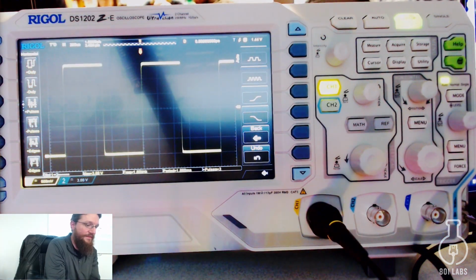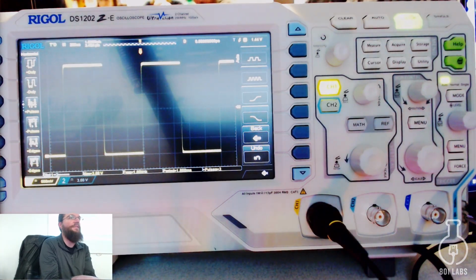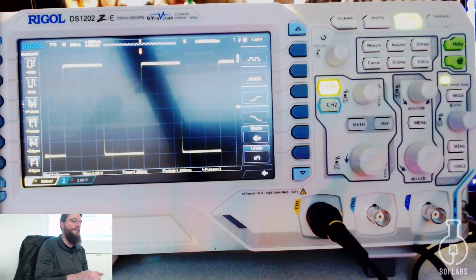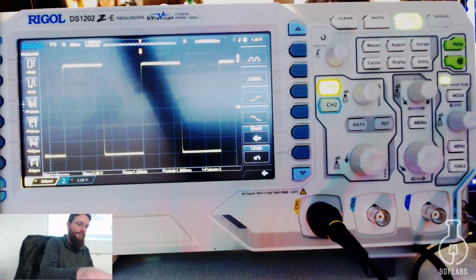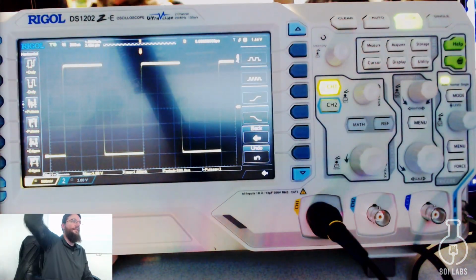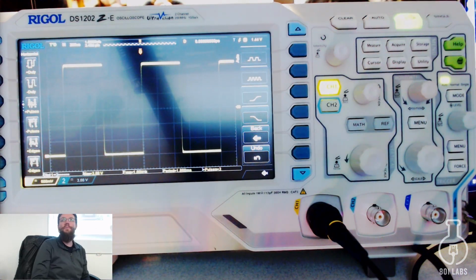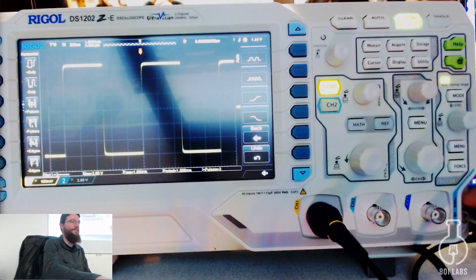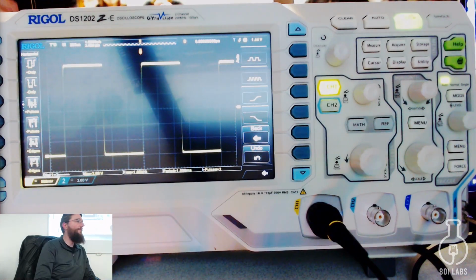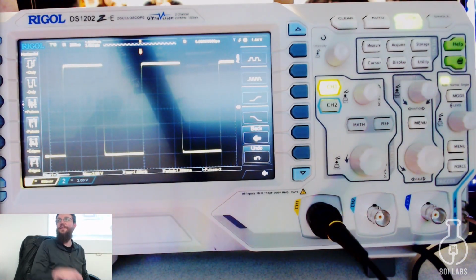And you adjust it, so that adjusts the capacitance of the probe to match the capacitance of the scope. And when I turn it, the transients on the ends of these are going to go way out of whack. So as long as the calibration signal that the probe's generating looks square. So the calibration is just, yeah, you calibrate the probe to match the capacitance of your scope when you get it, and it's in the instructions.